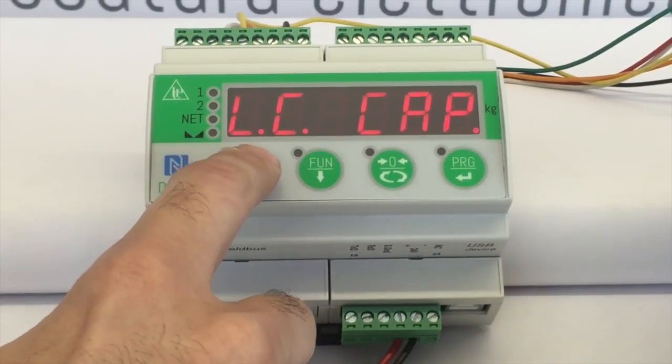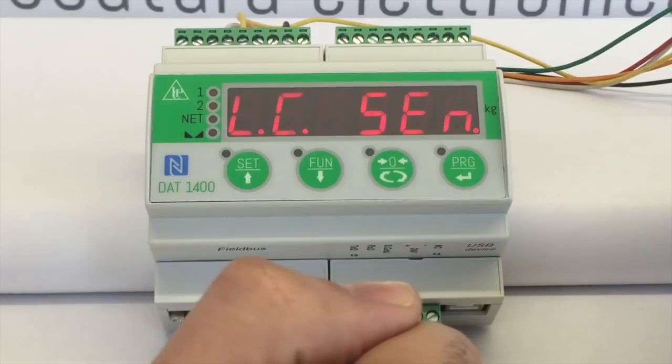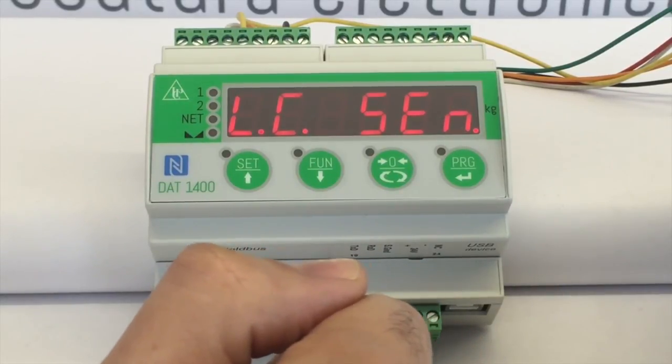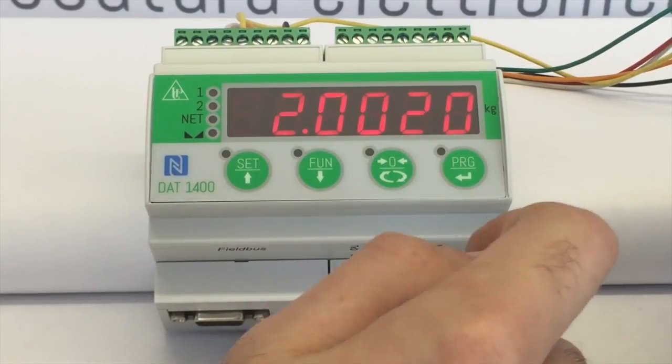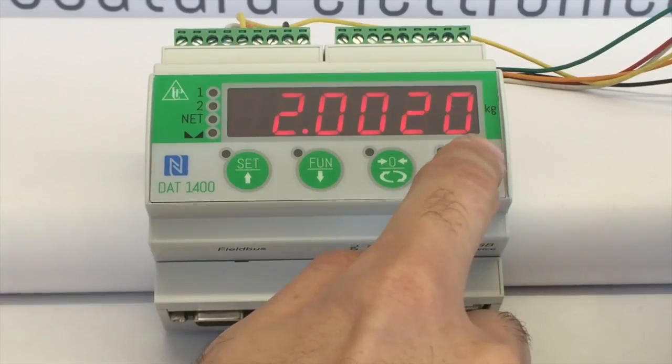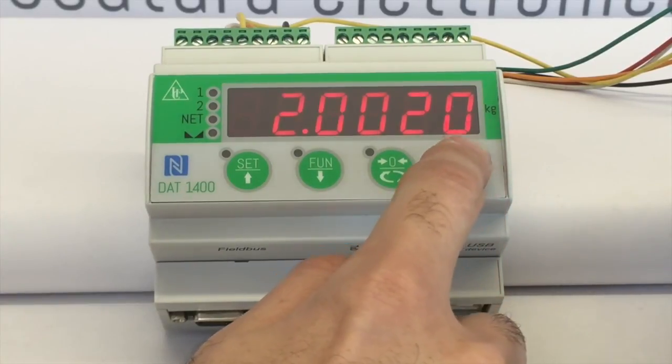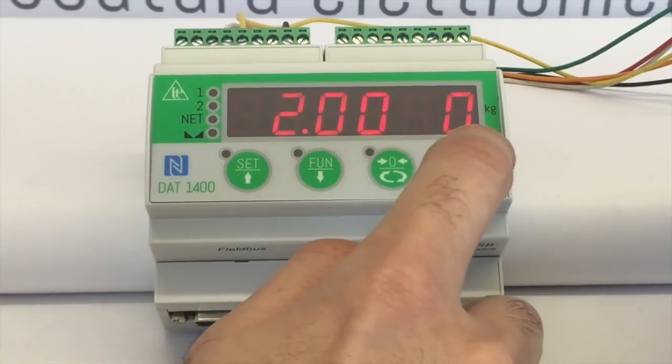Then set the next parameters by pressing SET. LC SENSE is the average sensitivity of the load cells. Again, open with PRG, set the digit to modify with PRG and increase or decrease with SET and FUN. Press PRG to confirm.